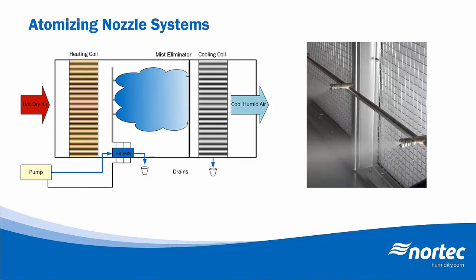So the next technology we'll look at is the atomizing nozzle system. So as I mentioned, this type of system works by spraying high pressure water directly into the airstream to be evaporated. Now, compared to an evaporative media system, these will typically consume more energy due to the water treatment system and the pump motor, but still much less than traditional DX cooling systems. So to give you an example, a system capable of producing about 1,700 pounds per hour will consume about 3 kilowatts of electricity, including the water treatment system.